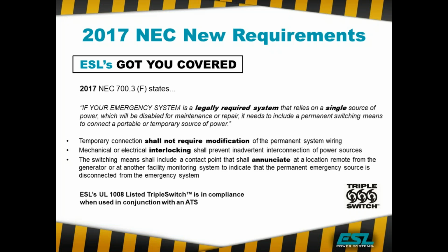Whatever you choose to do, you can't modify the permanent wiring system. It has to be something that you can tap into what's already there. Again, since you have now two power sources, they have to be mechanically or electrically interlocked to prevent both systems from being on at the same time. And you have to be able to tell the facility that the permanent generator, the primary source of backup power, is now offline. So you have to be able to send a signal to a remote annunciator saying that the permanent power is offline and we are now on portable or some other backup power.